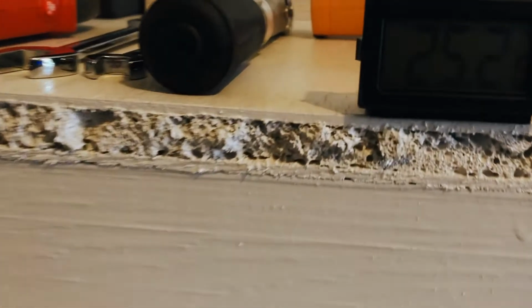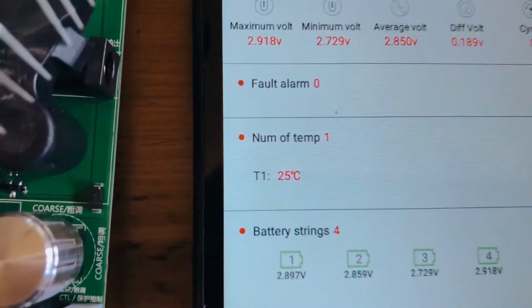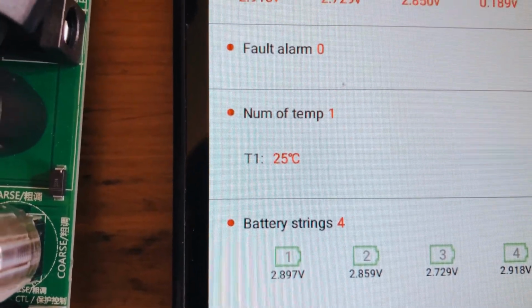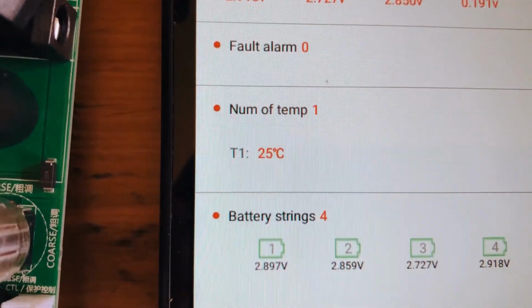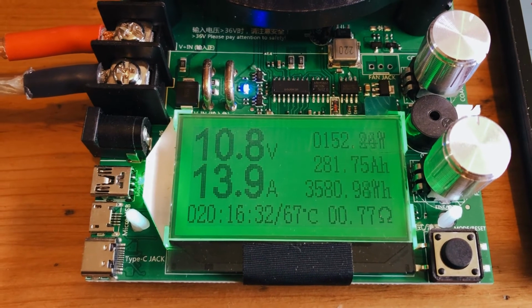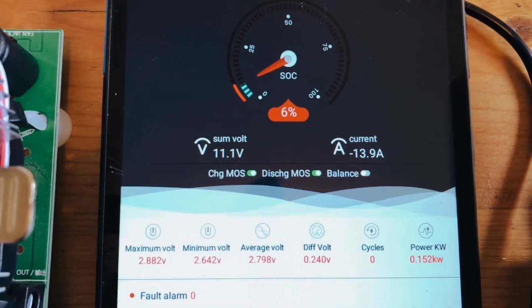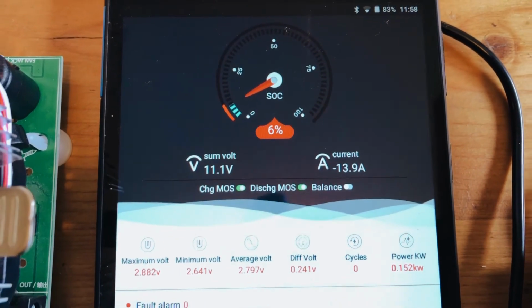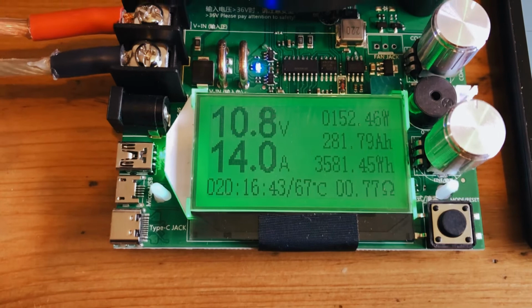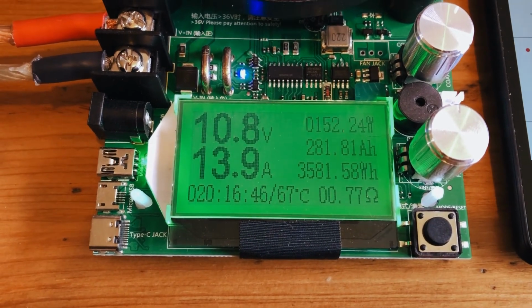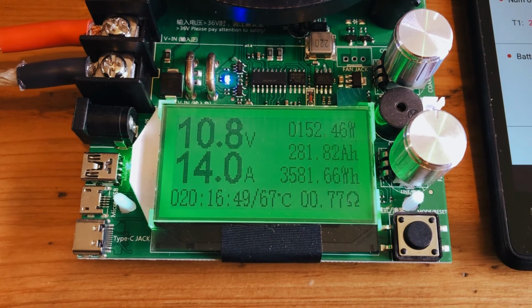The cells are sitting in a constant temperature environment, at 25.2 at the moment. And the BMS says that they are 25 degrees exactly, which is what we wanted to test at. So that's perfect. Cells sitting inside there. We've dropped below 11 volts at the tester, still sitting at 11.1 at the battery, according to the BMS. So by now, an inverter would have shut down because its safety threshold is 11 volts.